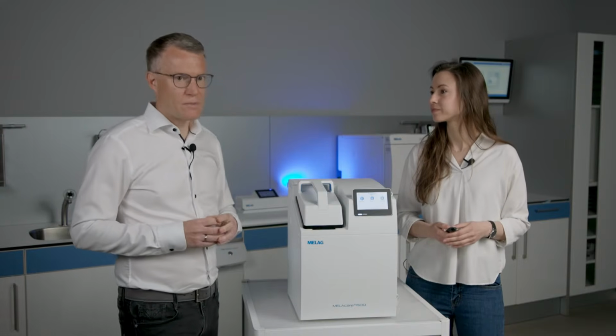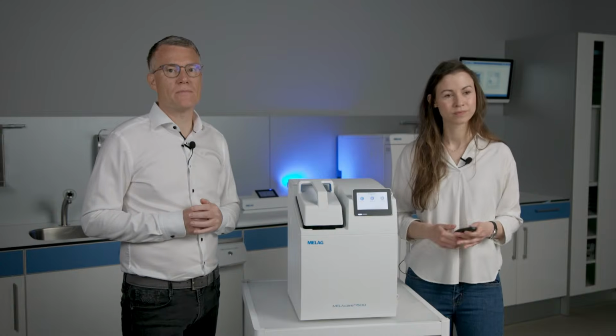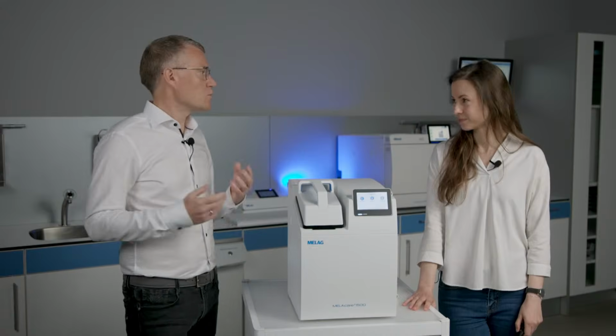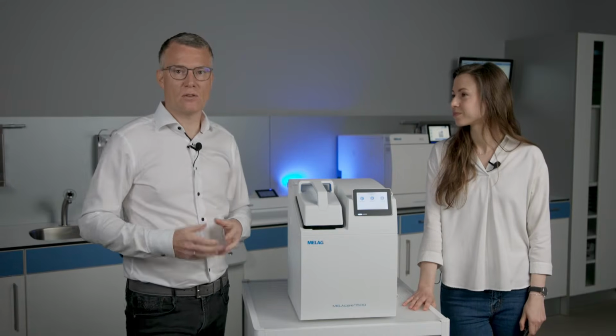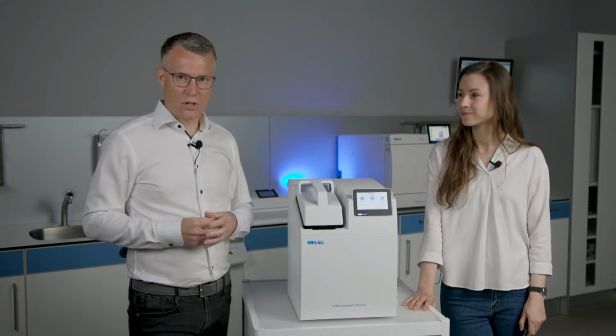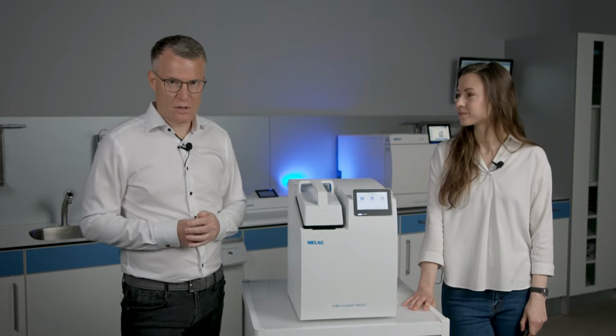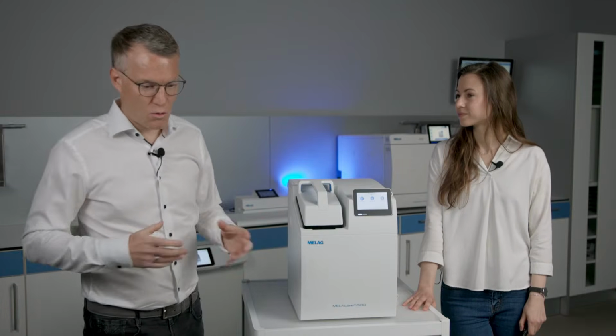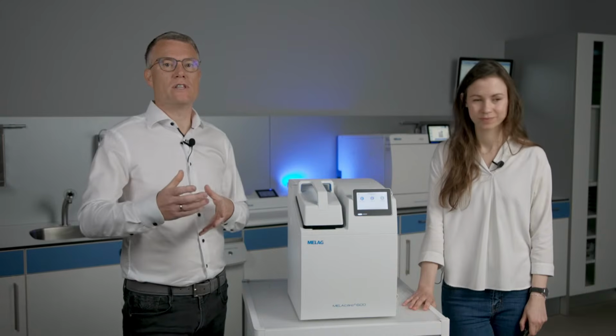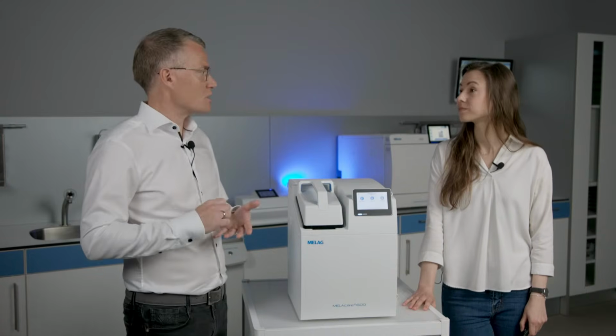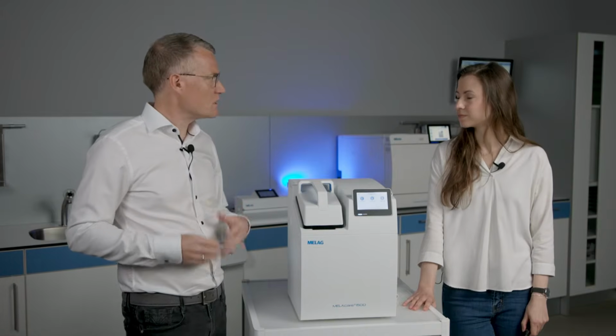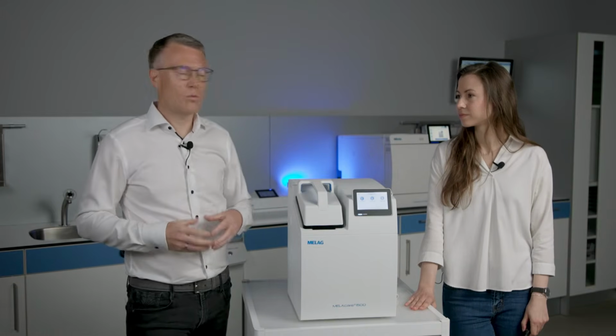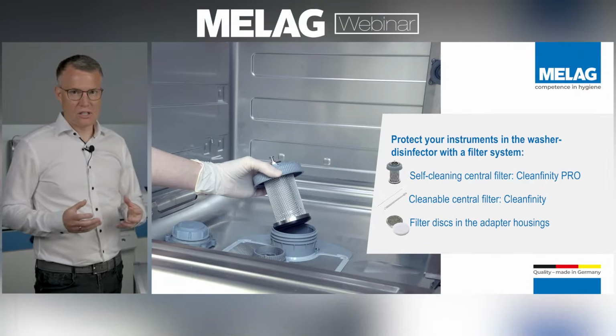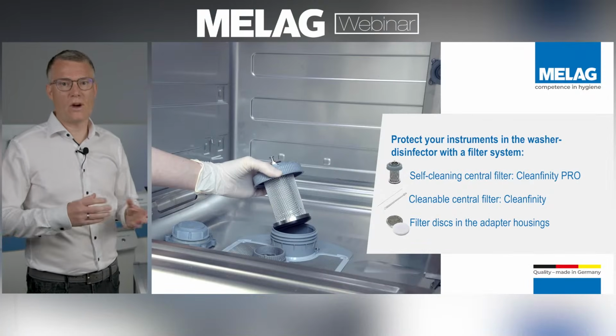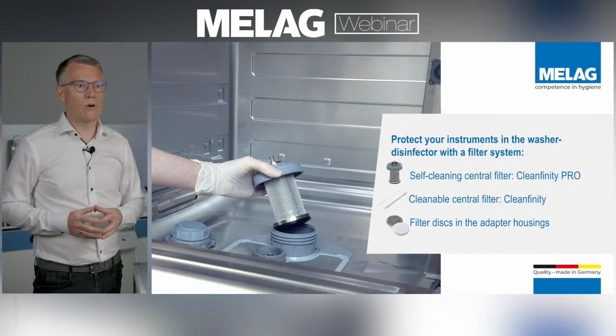One more important step is a filtering system. Once you are using some kind of automated process, and we're talking about water, for example, in a washer disinfector, and you have an injector rail with corresponding adapters to place your dental handpieces and turbines, you need to be sure that no residues in the water will be flushed with water pressure into your valuable instruments. So we need to take care that the water is filtered, and there are several technologies or ways to do it right available on the market.